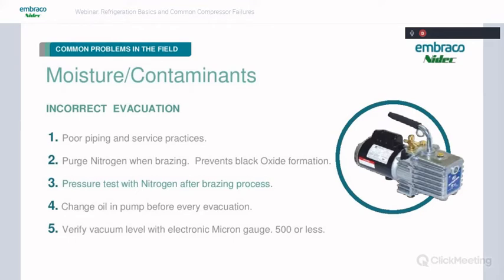And then after we braze, we want to make sure we pressure test with nitrogen. Make sure that everything's not leaking. This also absorbs any excess moisture. The nitrogen is going to help get any excess moisture out of there. I want to change the oil in that vacuum pump before every evacuation. A vacuum pump is not able to pull a good vacuum if it's got dirty, moisture-laden oil in it. It's not going to be able to really get a good vacuum on that system.